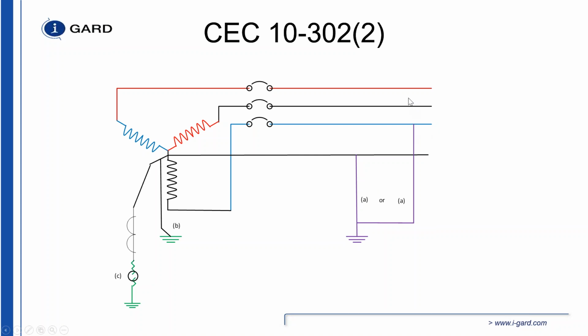If you have a fault as well on any of the phase conductors, you have to monitor that. And that's relatively easy to do. The neutral is a little bit trickier to monitor, but it can be done. If you had a ground fault on the wire connecting the source voltage to the resistor, if you had a ground fault on this cable, it must be monitored. Now this is different than having a distributed neutral and a ground fault here. Because if you did not have a distributed neutral, you would still have to monitor a ground fault on the cable connecting the resistance, the ground fault protection on this cable over here.